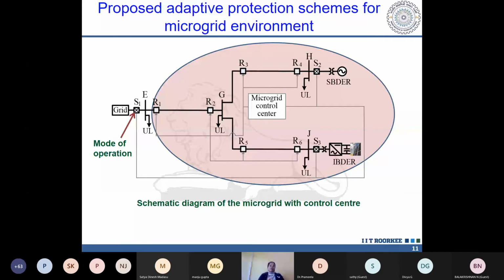So what will happen? Suppose, for example, my overcurrent relay setting is 2 ampere. But suddenly I see that the current magnitude has changed to 3 ampere. If I trigger my relay decision based on 2 ampere, it will maloperate, and as a result something may go wrong within my network. So it should be adapted - it should come to 3 ampere, not 2 ampere. That is what adaptiveness means. So in this process, the technique should always be ready to take the proper decision.